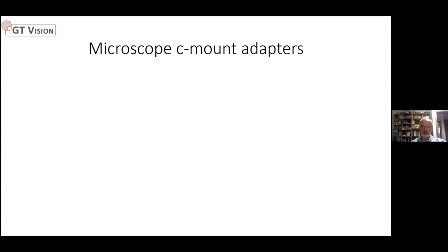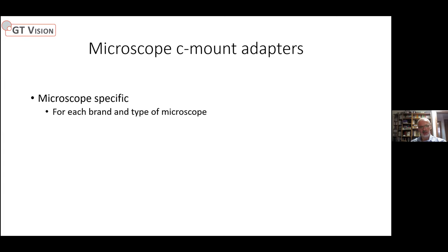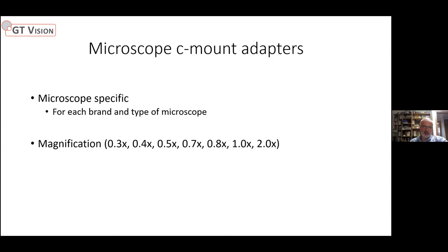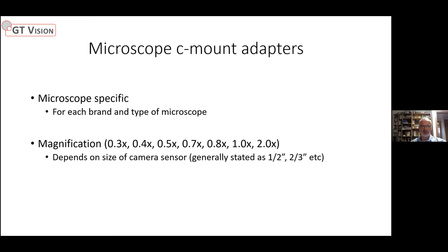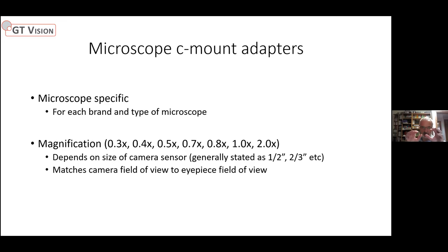So how do you decide? The c-mount adapter is microscope-specific — there'll be one for each brand of microscope and often each type. For instance, Leica will have a c-mount adapter for their upright microscopes, a different one for their inverted microscopes, and a different one for their stereo microscopes. The magnification also matters: you have a broad range from 0.3x up to 2x. You need to match the camera sensor size — generally stated in fractions of an inch — so the camera field of view matches the eyepiece field of view.